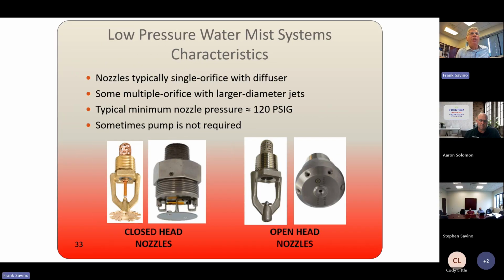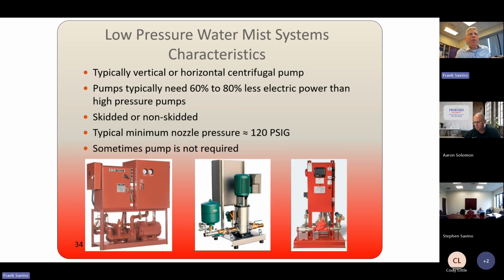And sometimes, a pump is not required. Say you've got city water coming into a building and you have 140, 150 PSI of city pressure, you can do a water mist system without even a pump. In fact, we did a survey not long ago just to get an idea, and I think we found somewhere around 25% of the time. We just looked at the static pressure in the buildings that we service, and 25% of the time they had enough water pressure just from the city to do a water mist system. So you would not even need a pump. You can do a vertical or horizontal centrifugal pump for a low pressure system. And again, a centrifugal pump consumes about 60 to 80% less electric power than a high pressure pump.